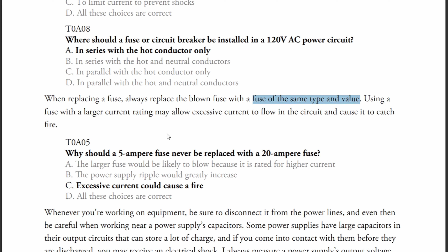You're going to cause issues if you put a larger fuse in there and go above 15 amps — the wires will start to heat up and eventually catch on fire. If you put a 10 amp fuse in a 15 amp circuit, you're going to be tripping it constantly, because your equipment is asking for 13 or 14 amps and you're only allowing 10 amps through. So yeah, you're not going to have fun.